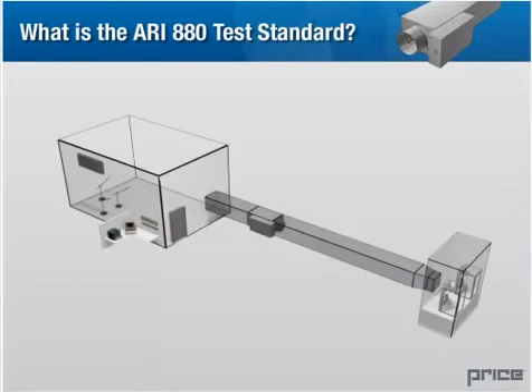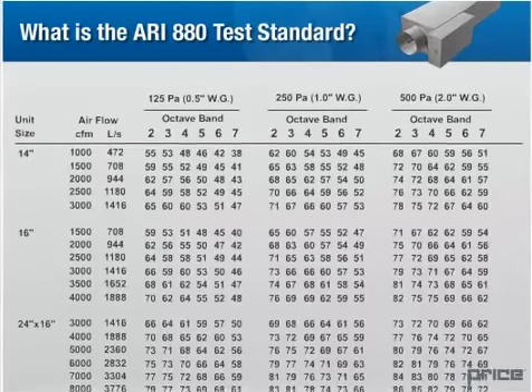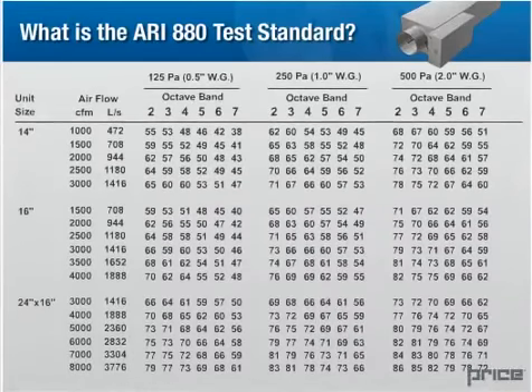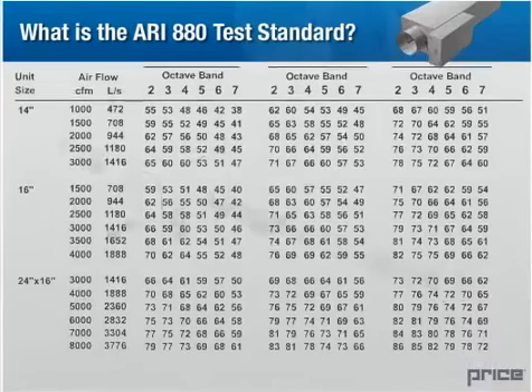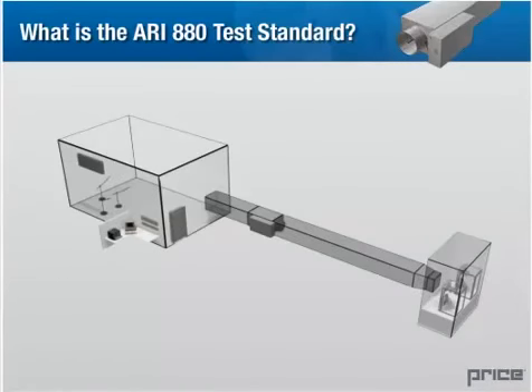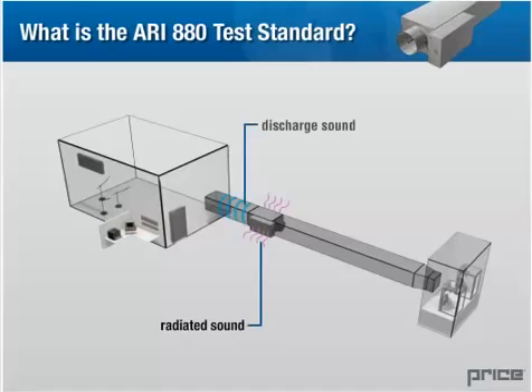The sound power data generated in the test setup is tabulated for the given inlet duct pressure and flow ratings of the terminal unit. In the course of testing the terminal unit, we determine the amount of radiated sound and discharged sound that is produced. For the purposes of this training module, we'll focus on the discharge sound of the terminal units, that is, the sound traveling downstream through the ductwork into the occupied space. NC levels.